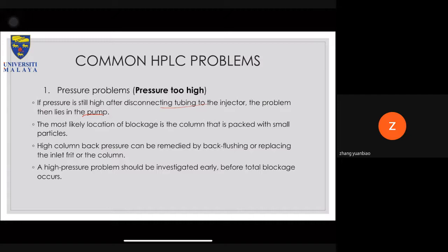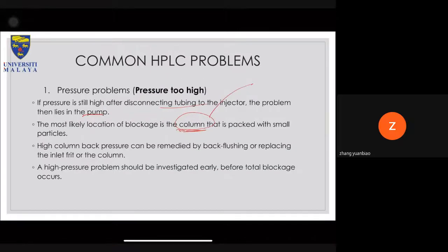Okay, so that's what I mean. Most commonly it is the column, but if you have a column guard, then it will be the column guard. And if you have an inlet filter, then normally the problem will be here. So that's the order: normally the inlet filter will be blocked first, then your column guard, and then your column.